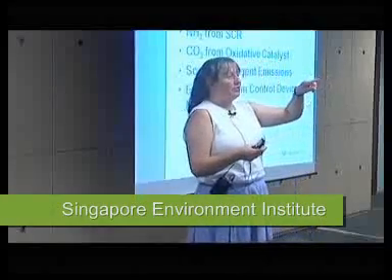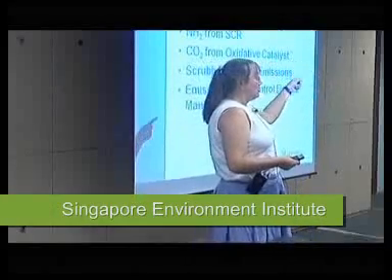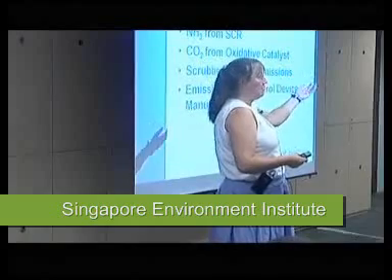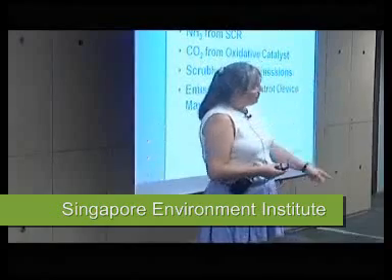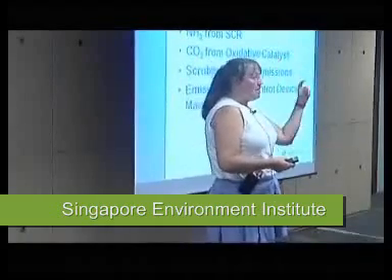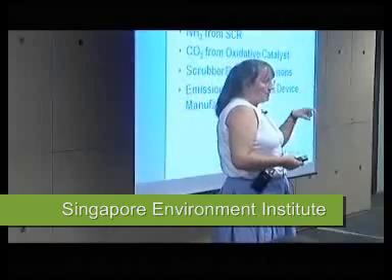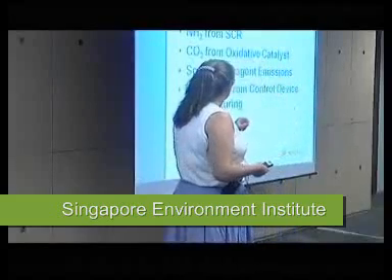You read the actual concentration, and there's a feedback loop into your ammonia injection grid that says either give us more ammonia or less ammonia. Then you go through this continuous feedback, so you always have a little bit of extra ammonia coming through the system. So you have ammonia slip.